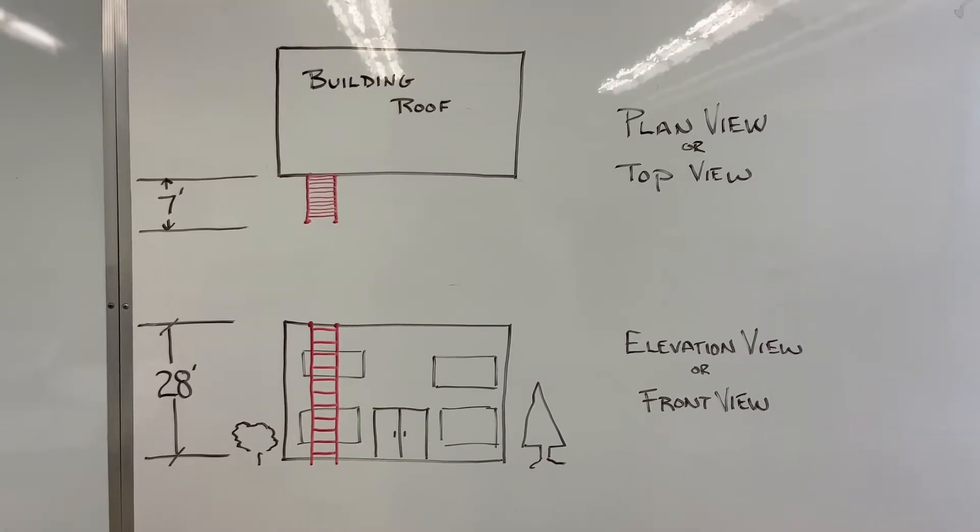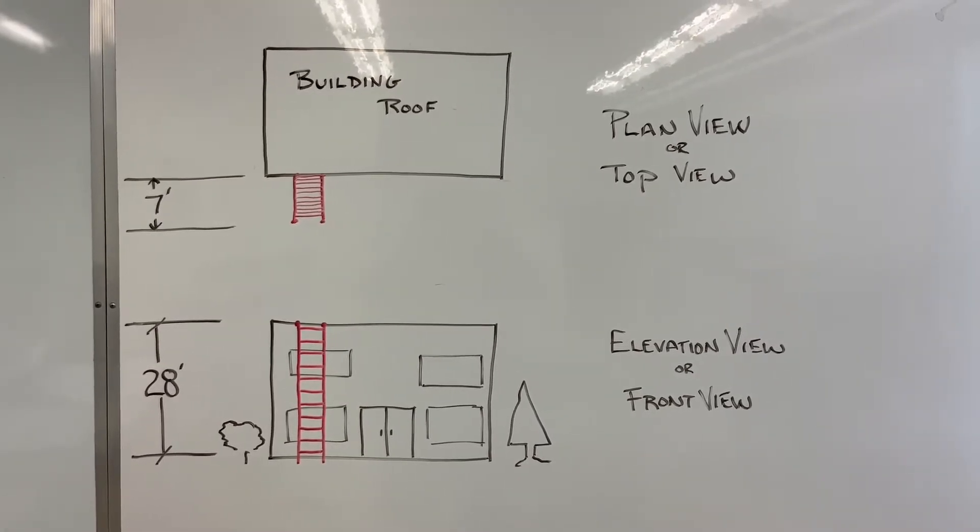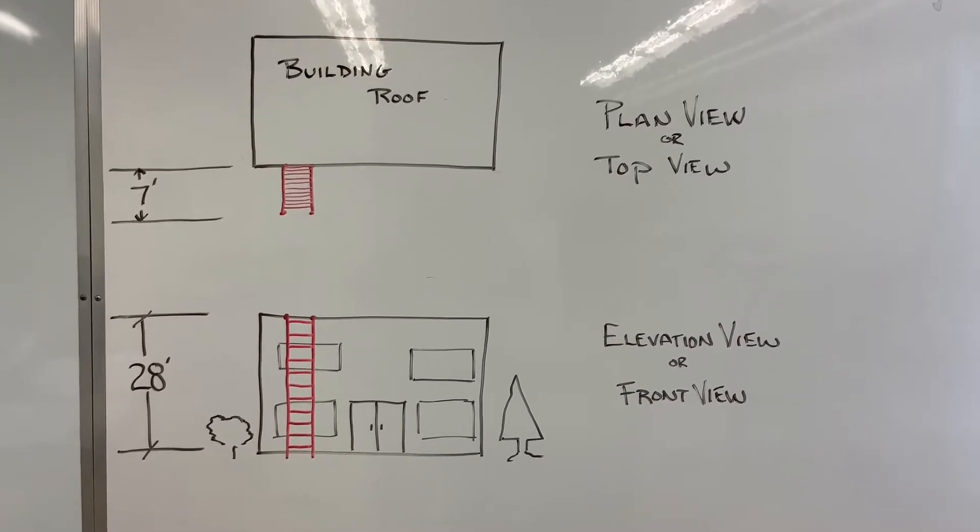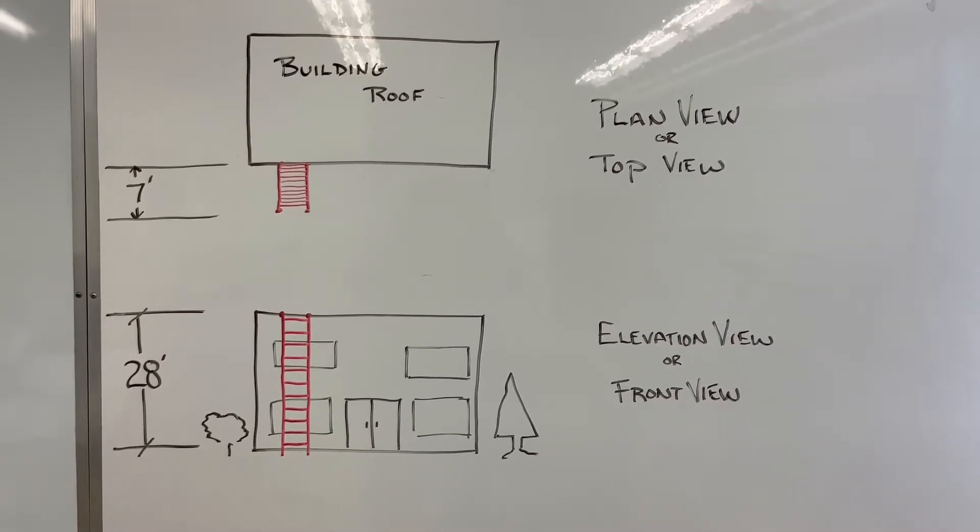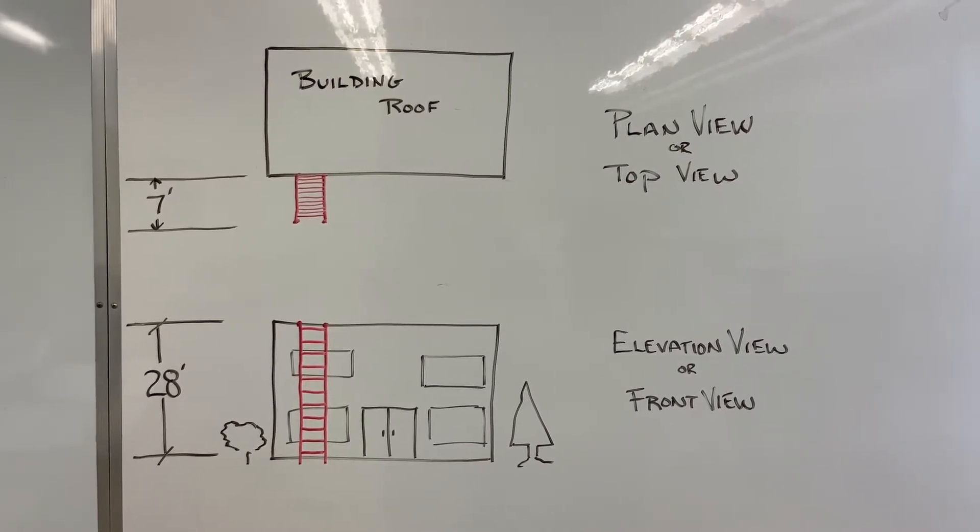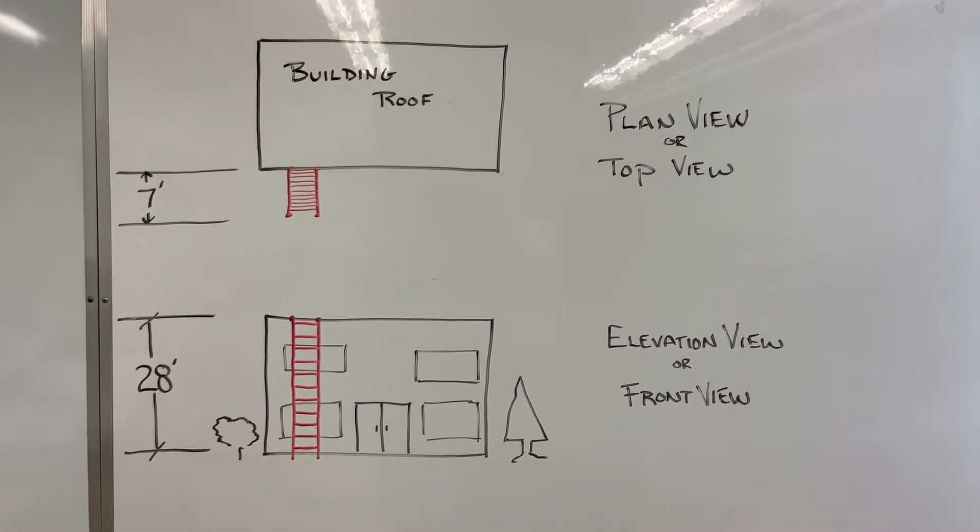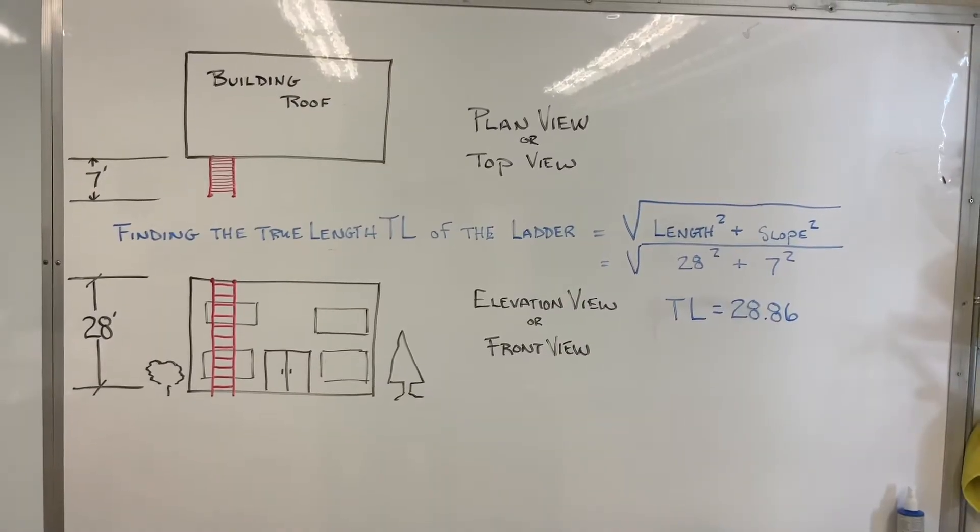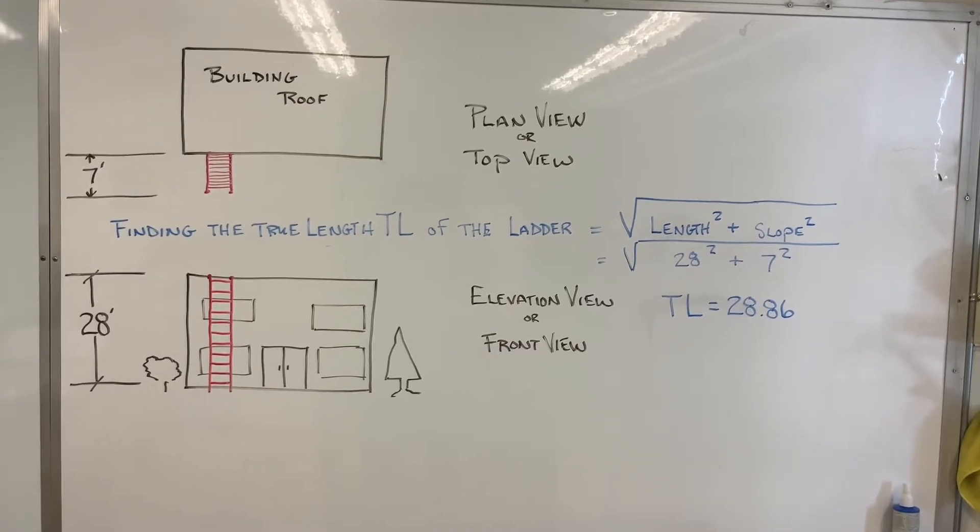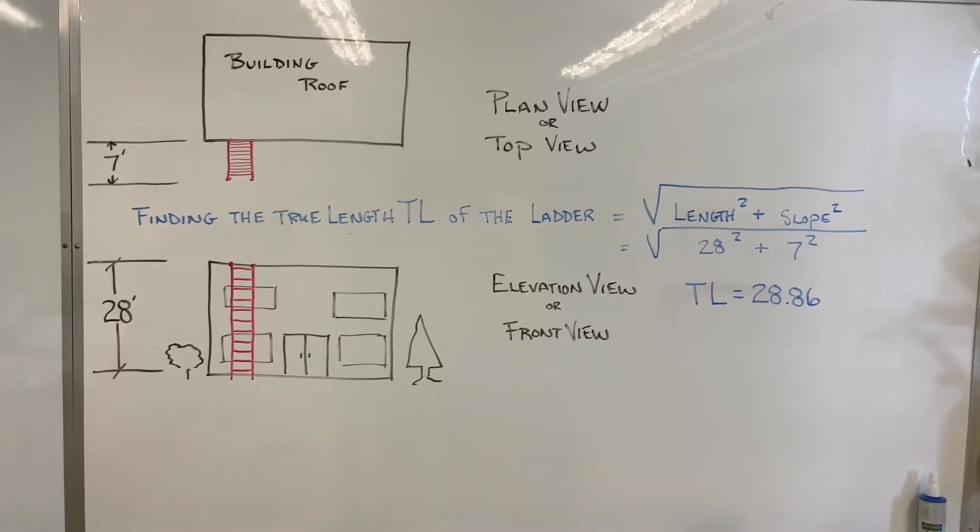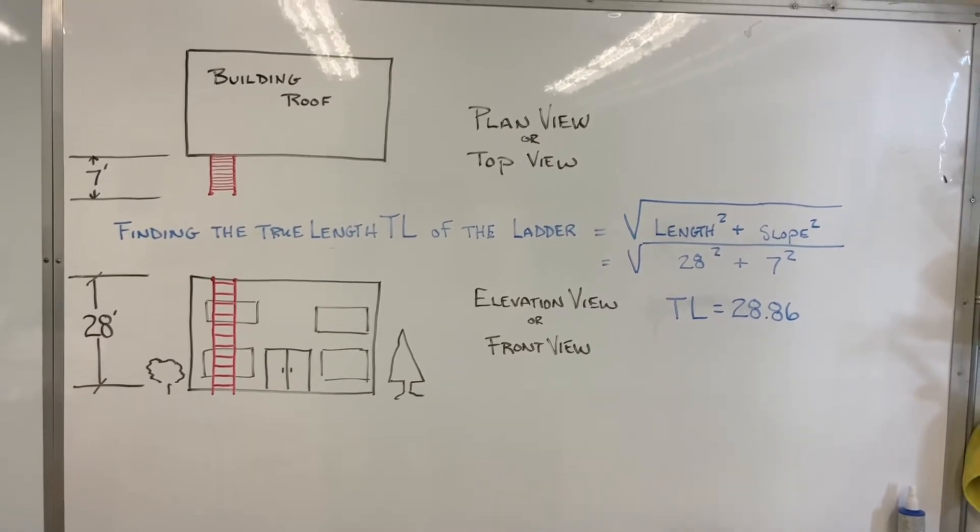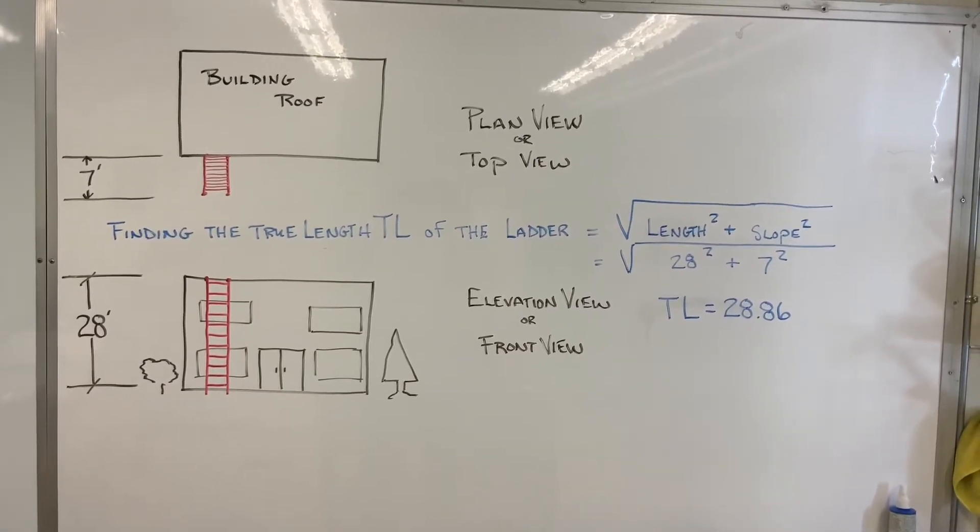In sheet metal, we use triangulation in pattern drafting to develop patterns for objects that have slanted sides. In order to lay out these patterns, you must find the true length of each side. This is the formula that we would be using: the square root of the finished length squared plus slant squared, or slope or change squared.